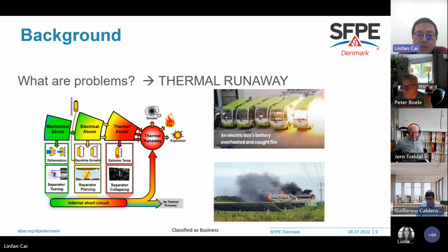When the combustion condition is met, fire will initiate from the first damaged battery cell, leading to the heating or thermal abuse of adjacent batteries. This is how thermal runaway propagates to adjacent battery cells, to the modules, even to the racks, and so on and so forth.